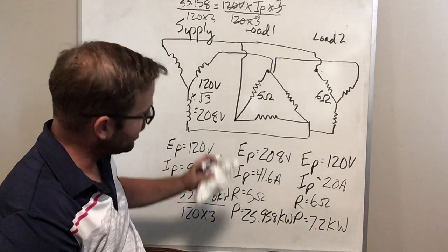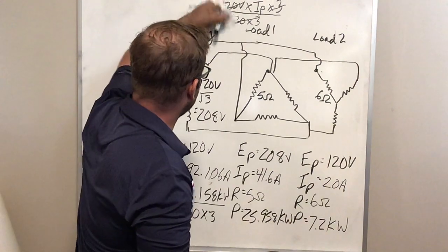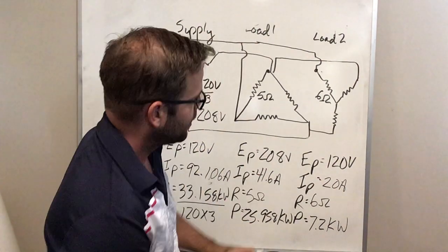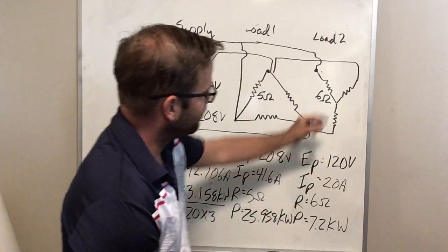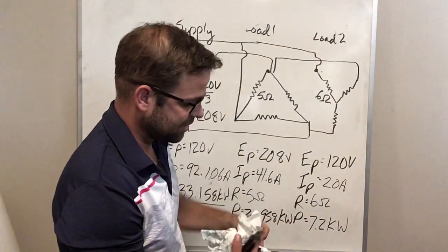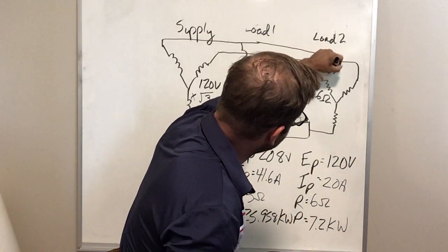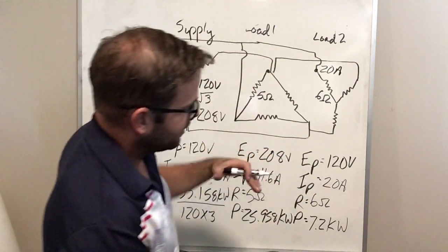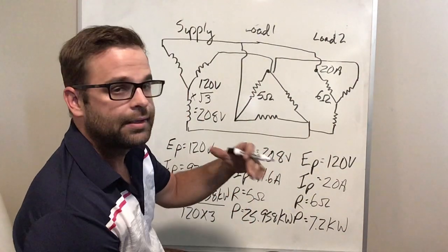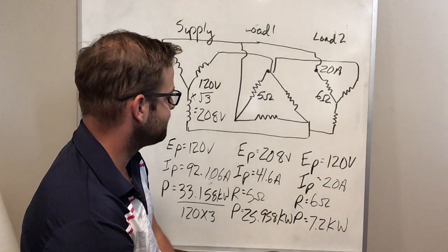And for those who like also to do it or want to see it being done the other way as well, if we went to take an amp clamp and put an amp clamp on there, we saw 20 amps. We come onto line, means that it's also 20 amps. So we have a line current of 20 amps in Y, and as the Y formula indicates, the current in the line and the current in the phase are the same.